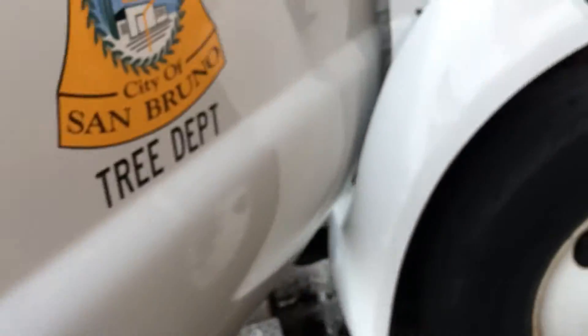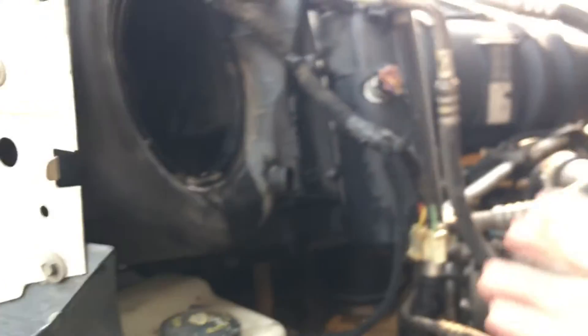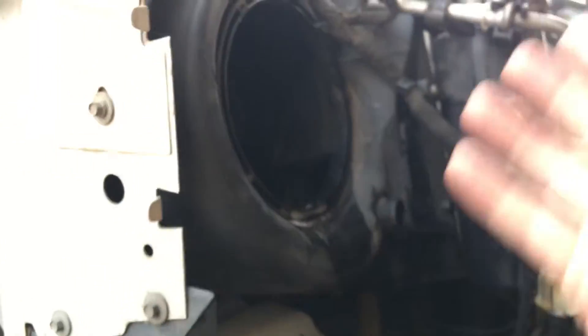The plastic on the bottom only — it spills over right here, comes down and comes right out, kind of like your old 1950s, 60s, and 70s pickup trucks that didn't have carpet back in those days. So now I can actually check the system, because the airflow was so blocked it didn't matter if you had a correct charge — it wouldn't work anyway because of a plugged-up evaporator.